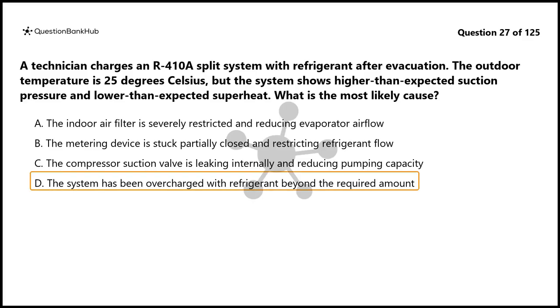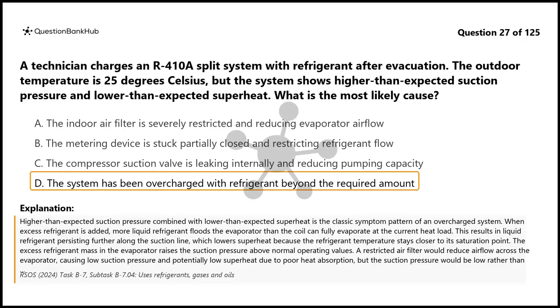The correct answer is D. Higher than expected suction pressure combined with lower than expected superheat is the classic symptom pattern of an overcharged system. When excess refrigerant is added, more liquid refrigerant floods the evaporator than the coil can fully evaporate at the current heat load. This results in liquid refrigerant persisting further along the suction line, which lowers superheat because the refrigerant temperature stays closer to its saturation point. The excess refrigerant mass in the evaporator raises the suction pressure above normal operating values.